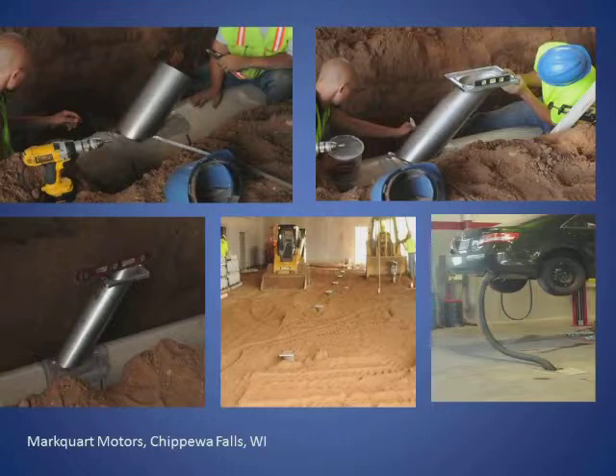Terry, we had a question on this slide here. Why not use PVC plastic? They use it underground for plumbing all the time. Because the temperature requirements for vehicle exhaust are too high. PVC can melt at 140 degrees. CPVC is rated at 180. And we've tested ours, as you'll see later, up to really 700. But we've estimated that a typical vehicle exhaust system can see 325 degrees possibly. So that's the reason for not using PVC.